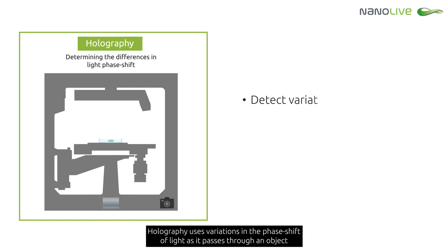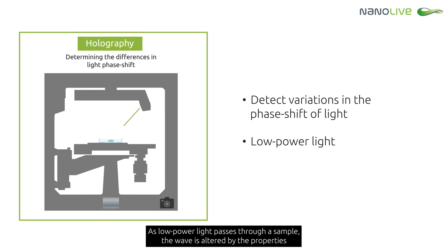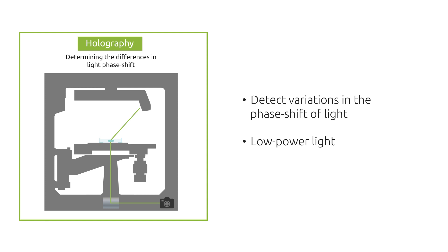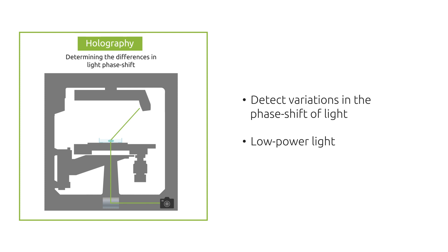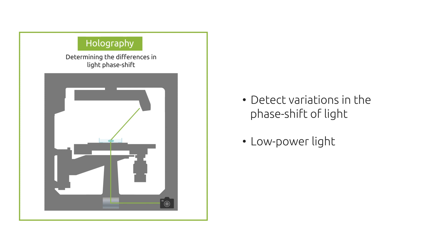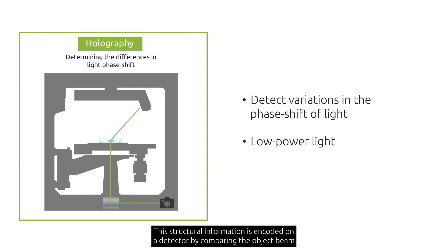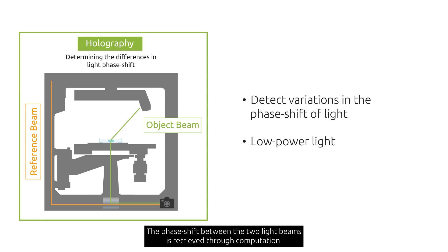Holography uses variations in the phase shift of light as it passes through an object to produce quantitative images. As low-power light passes through a sample, the wave is altered by the properties of the sample's internal structure. Cellular structures and organelles interact with light in different ways, meaning they can be differentiated by their refractive index values. This structural information is encoded on a detector by comparing the object beam with a reference beam, and the phase shift between the two is retrieved through computation based on the recorded hologram.